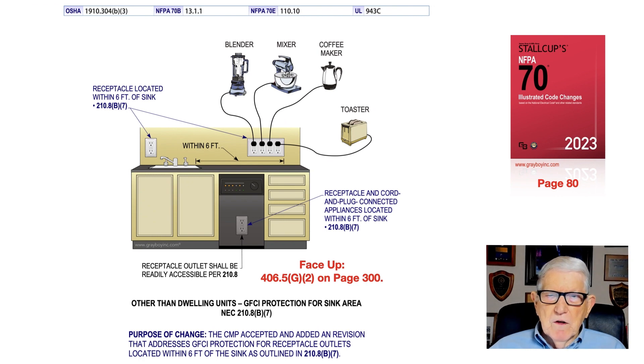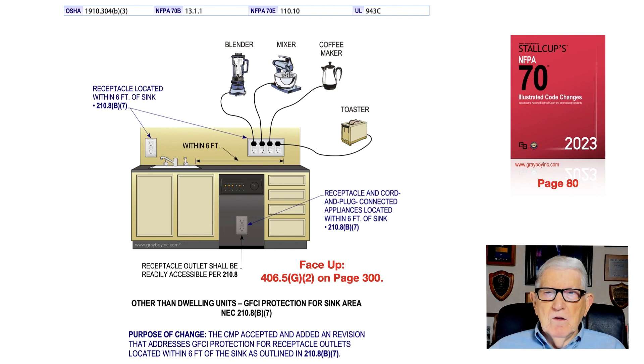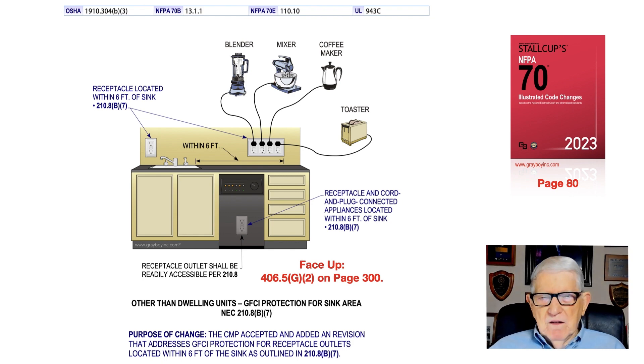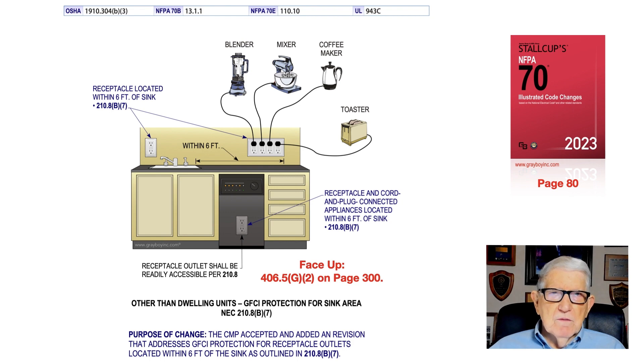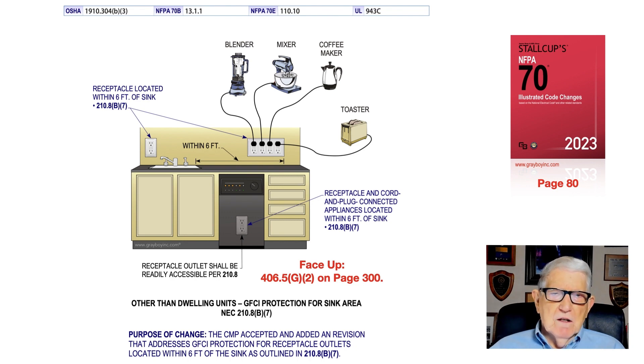This illustration also deals with other than dwelling units — GFCI protection for the sink area in accordance with 210.8 B7. The code making panel accepted a revision addressing GFCI protection for receptacle outlets located within six feet of the inside wall of the sink. Four receptacles shown in the illustration are within six feet of the sink and must be GFCI protected for personnel using blenders, mixers, coffee pots, toasters, and similar appliances in and around a wet sink area.